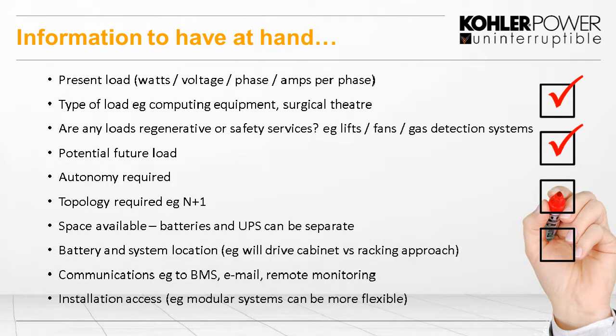You also have to say how much space you have available for the batteries and UPS. These can be put in separate places. Where's the battery going to be located? Because this will drive how we're going to install it. Are we going to put it in a cabinet or are we going to put it on a rack? And if the unit is remote, most people now will have communication with the UPS, either connected to their BMS or emailing an issue through network cards, and it can even be remote monitored by your supplier. And depending on where you put it, installation access may well be a consideration. And again, modular systems that can be broken down can make that situation much easier.